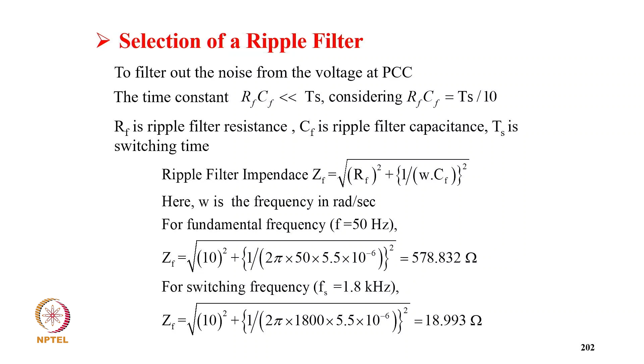For fundamental frequency of 50 Hz, ZF, putting the value, comes 578.832 ohm, and for switching frequency of 1.8 kHz, putting the value, we get ZF equal to 18.993 ohm. Now selection of the ripple filter, considering the switching frequency Fs equal to 1.8 kHz, the ripple filter parameters are RF equal to 10 and CF equal to 5.5. The impedance offered for the switching frequency is 18.993 ohm, and the impedance offered to fundamental frequency is 578.83, which is sufficiently large, and hence the ripple filter draws negligible fundamental frequency current.